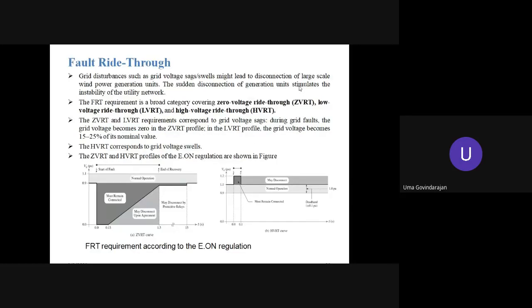Let me go into detail about fault ride through, FRT. Fault ride through is a point for grid connected machines, grid connected wind electric generators. Grid disturbances such as grid voltage sag and swell might lead to disconnection of large scale wind power generation units. Meaning a 10 megawatt generator connected to the grid may be transporting 10 megawatt of power at normal conditions. Suppose due to some fault in the transmission line or in another part of the network the grid voltage falls, there is a possibility for the 10 megawatt wind turbine to come out of synchronism at the PCC.